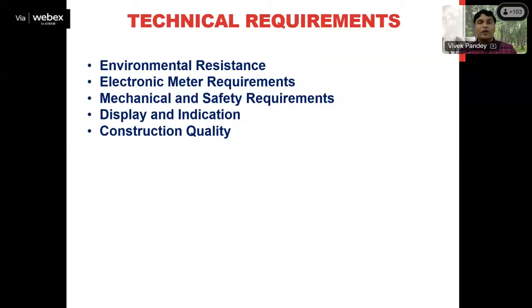Next technical requirement is related to the mechanical and safety requirements, where the meter body must withstand 1.5 times the maximum working pressure. So if a specified pressure range is there for a gas meter, 1.5 times the maximum pressure is applied on the gas meter, and we check whether it is able to withstand that mechanical surge or not. Then we will also check whether the gas meter is gas tight and water resistant or not. Then we will also check it for an anti-tamper seal, and it should have visible verification marks.